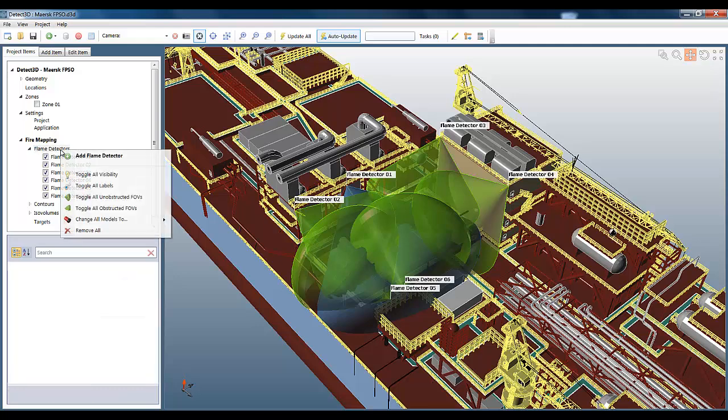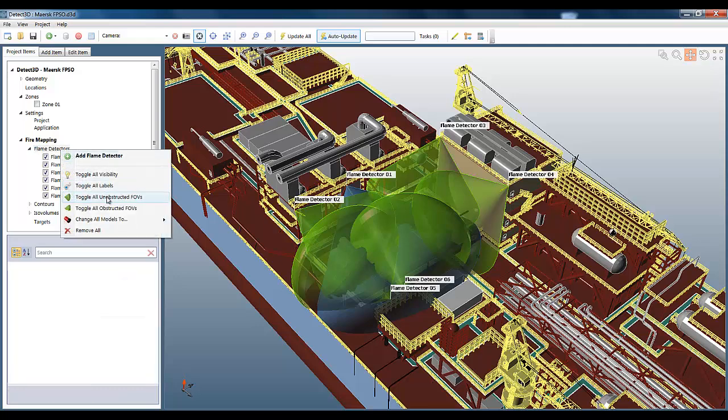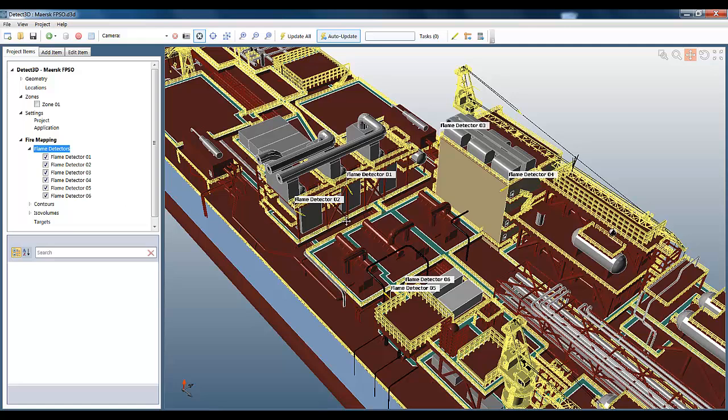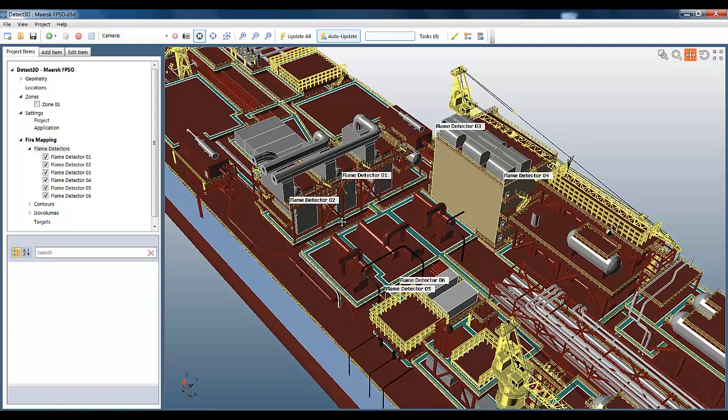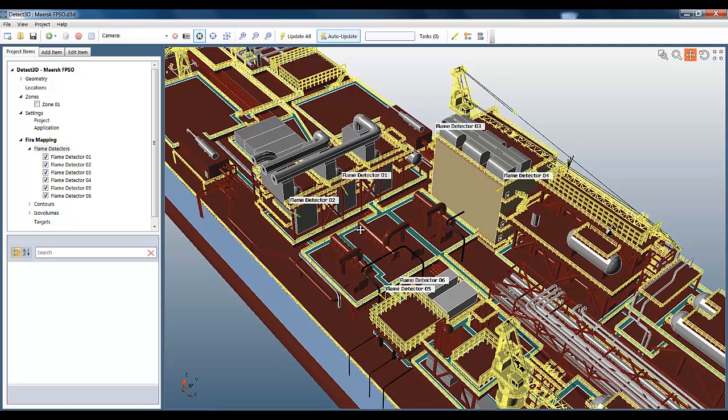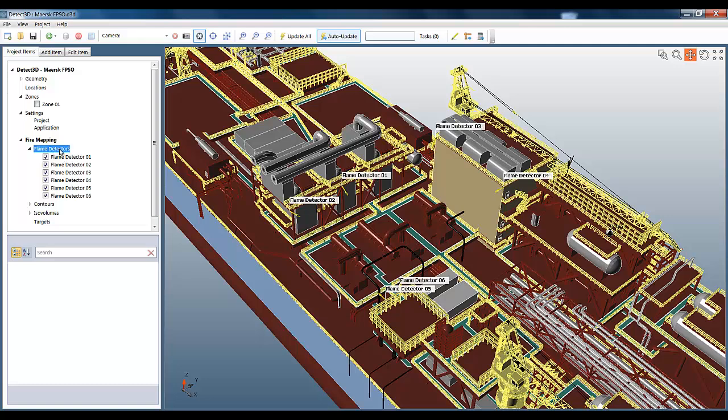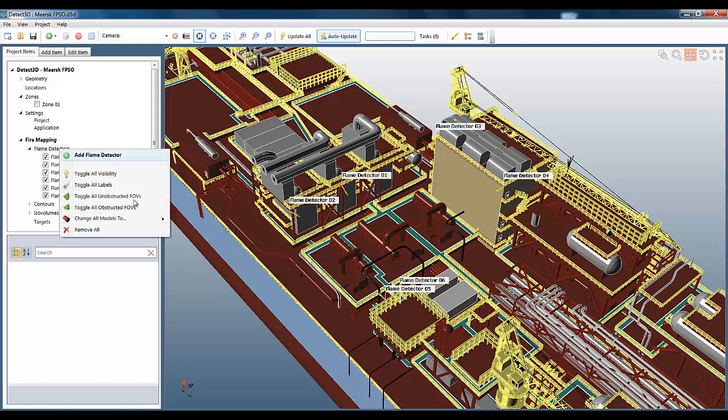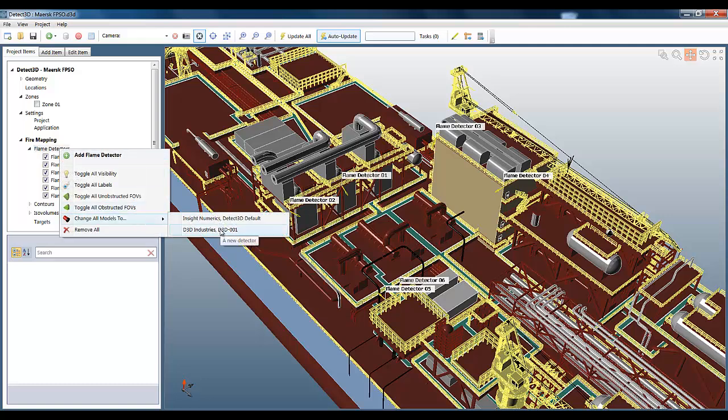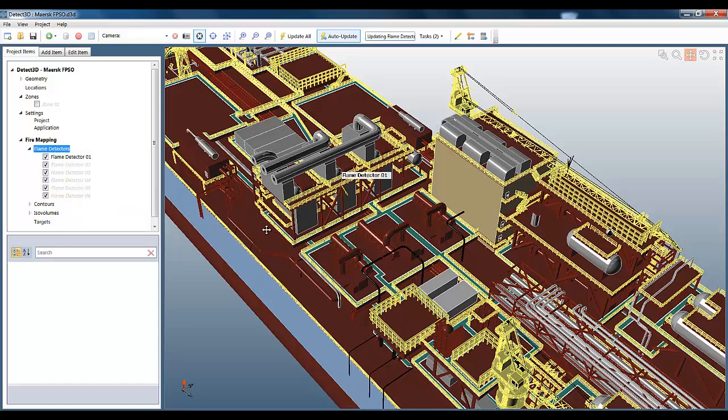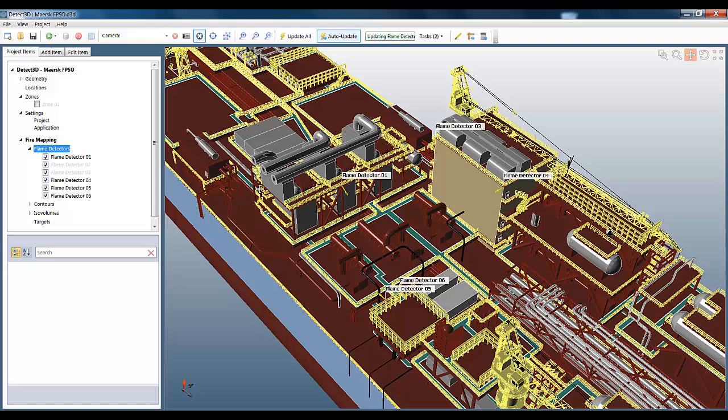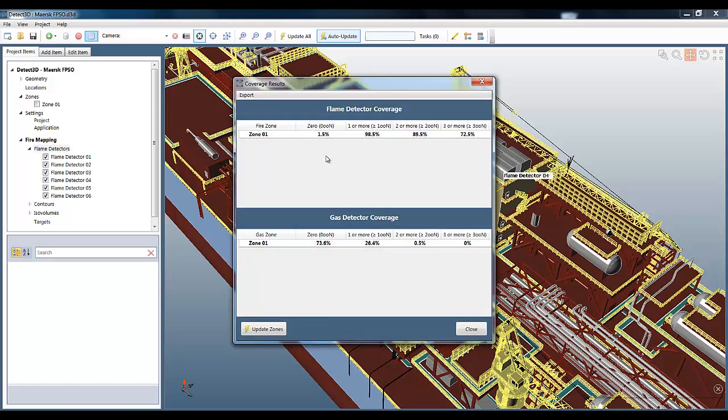So this demonstrates the fact that you can have different models in one simulation without any problem, but the real power is being able to change all the flame detector models at once, and I can easily do that by right-clicking, selecting Change All Models To, and then selecting the new model that I created. You can see the project is automatically updating. The grayed-out text means that the object is not up-to-date. The flame detectors are actually updating themselves in parallel, and all the coverage statistics are automatically updated. You can see zeroes down at 2%, and three or mores up at over 70%.